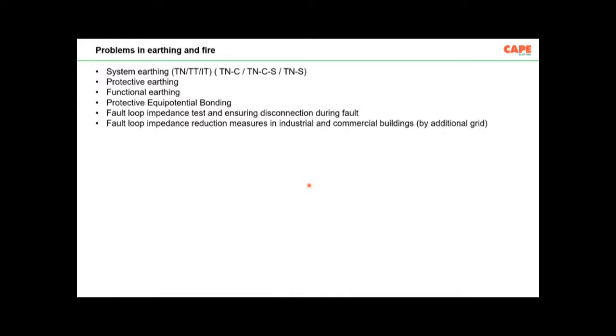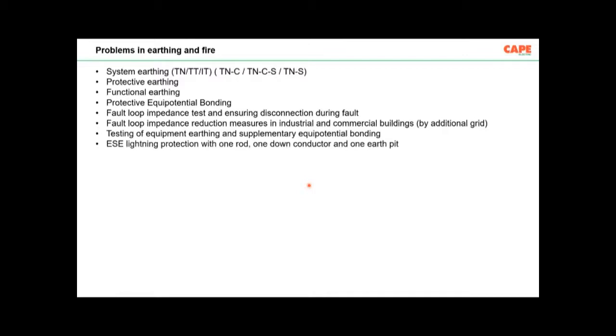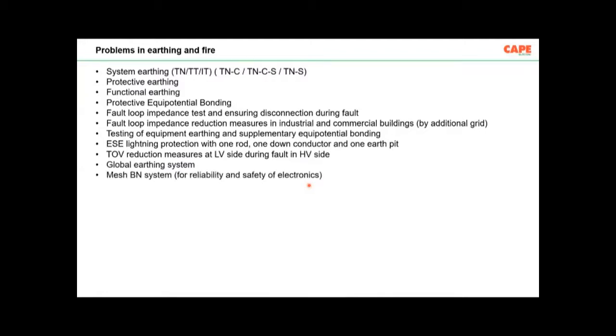Fault loop impedance reduction measures in industrial and commercial buildings by an additional grid is also a problematic area. Testing of equipment earthing and supplementary equipotential bonding: for example, if you have a lift, a large machine, or an operation theater, supplementary equipotential bonding and continuity resistance measurements we rarely do. Early streamer emission lightning protection with one rod, one down conductor, one earthing is followed. Temporary overvoltage reduction on the low voltage side of a transformer during a fault on the HV side is generally not carried out. Global earthing systems are not followed. Mesh bonding systems are not followed. Actually, a good earthing means all the above.